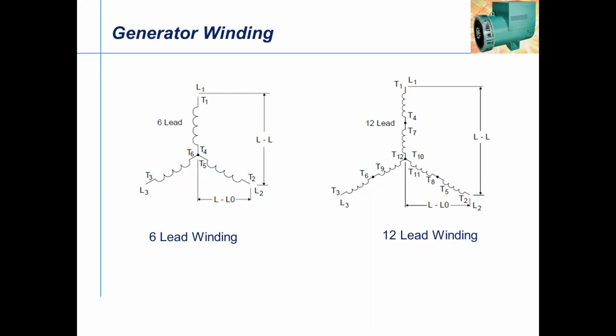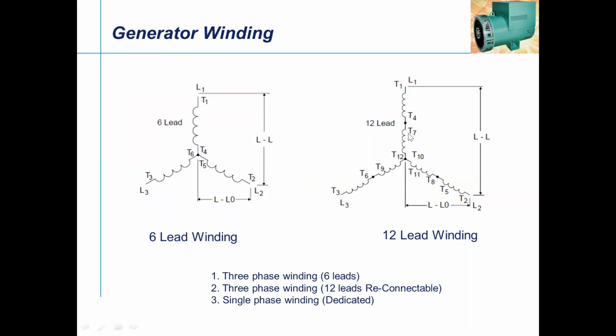For the voltage, what we have discussed previously, it is 230 volts, or a 3-phase 3-wire system, or a 3-phase 4-wire system. Generally, this is a 6-lead connection and 12-lead connection, where the neutral will be taken from the star point. So this is how it goes. And there are 3-phase 6-lead and 3-phase 12-lead connections, where you can do a multi-voltage connection, and a single-phase dedicated winding for the telecom application and the commercial household requirements. We have a dedicated single-phase winding.